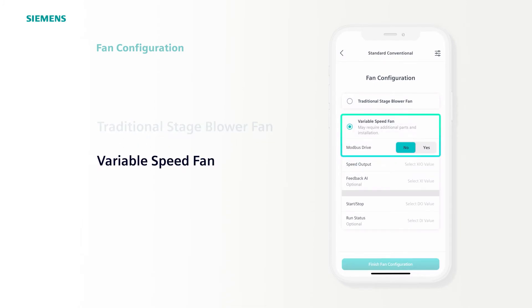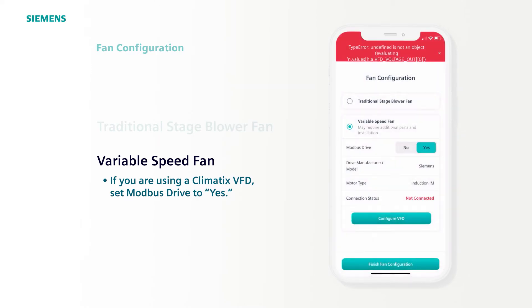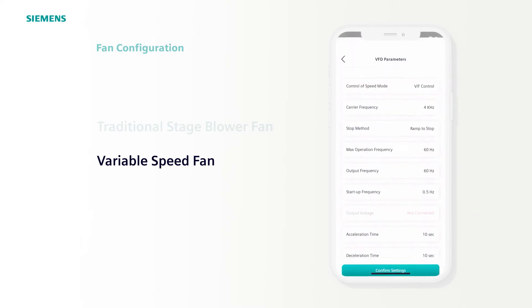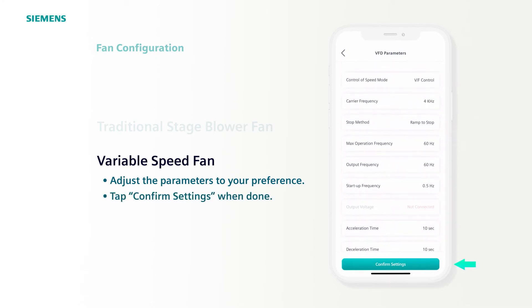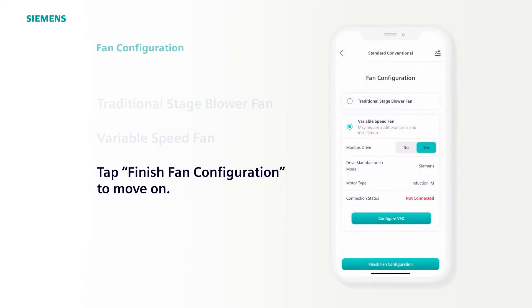If you've selected variable speed fan and you use a Climatix VFD, select Yes for Modbus Drive. You'll notice this example showed an error because we are not connected during this demonstration — you should not see an error when connected. Now, select Configure VFD. There are several adjustable parameters for controlling your VFD, though the default settings typically don't need to be changed. If you like what you see, tap Confirm Settings. Then tap Finish Fan Configuration to move on.